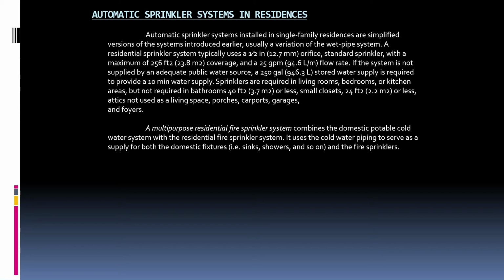Automatic sprinkler systems in residences. Automatic sprinkler systems installed in single-family residences are a simplified version of the systems introduced earlier. Usually a variation of the wet pipe system, a residential sprinkler system typically uses a one-half inch orifice standard sprinkler with a maximum of 256 feet squared coverage and a 25 GPM flow rate.